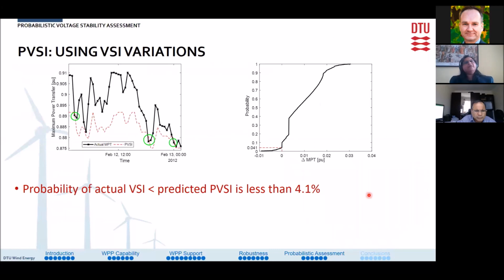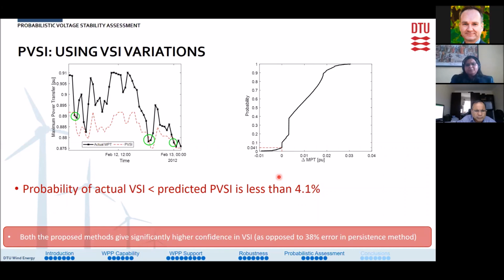Looking at the results for this methodology, we see something similar, but in this case there are fewer values of the voltage stability index that are less than the predicted value. The error analysis shows the probability of the actual index being less than the predicted value is less than 4.1%. So both proposed methods give significantly higher confidence in the voltage stability index as opposed to the 38% error in the persistence method. The second methodology is somewhat better, but the computational complexity involved in its implementation, especially on large power systems, may make it less preferable compared to the first method.